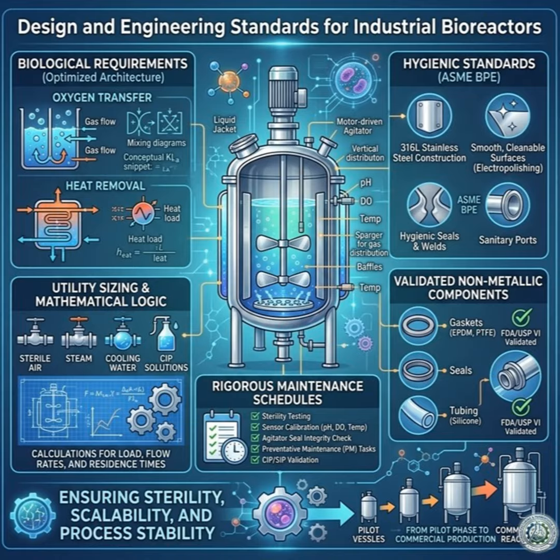about how a biomanufacturing facility has to treat these replacement parts. You can't just run to a local hardware store and grab a rubber O-ring that looks like it fits. The regulatory agencies would shut you down immediately. Every consumable part must be a heavily qualified item. That means it needs a documented part number, a strict proactive replacement interval based on validation testing, and rigid change control records. A paper trail for every single piece of rubber.